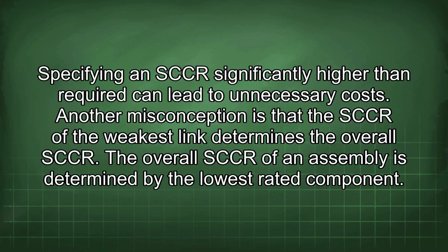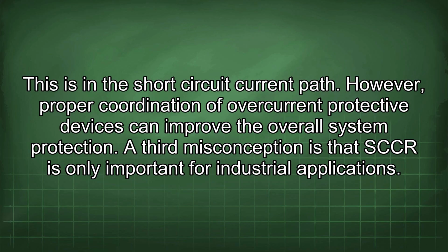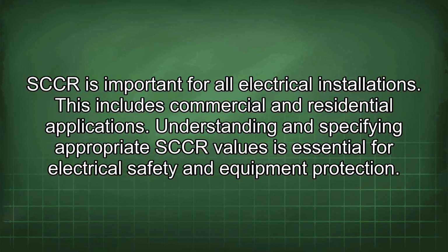Another misconception is that the SCCR of the weakest link determines the overall SCCR. The overall SCCR of an assembly is determined by the lowest rated component in the short-circuit current path. However, proper coordination of overcurrent protective devices can improve the overall system protection. A third misconception is that SCCR is only important for industrial applications. SCCR is important for all electrical installations. This includes commercial and residential applications.